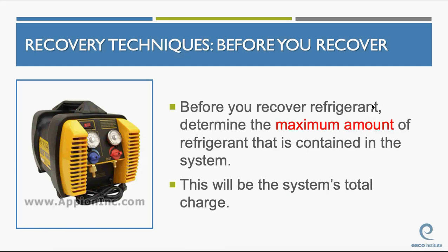Before you recover refrigerant, you must determine the maximum amount of refrigerant that is contained in the system. That will be the system's total charge. I have to know how much refrigerant is in there before I recover it because I have to make sure my recovery cylinder has enough room in it for that total charge. By the way, I think we're around page 21 in your manual, someplace right around there.